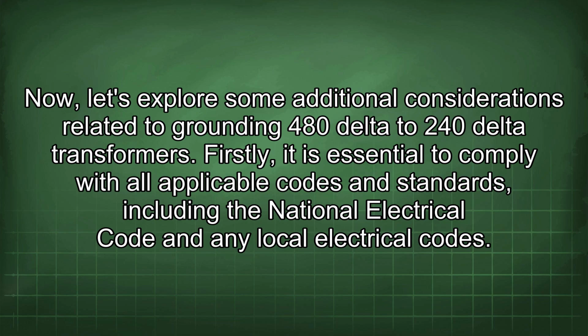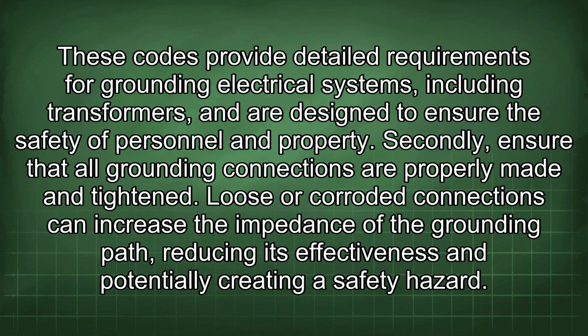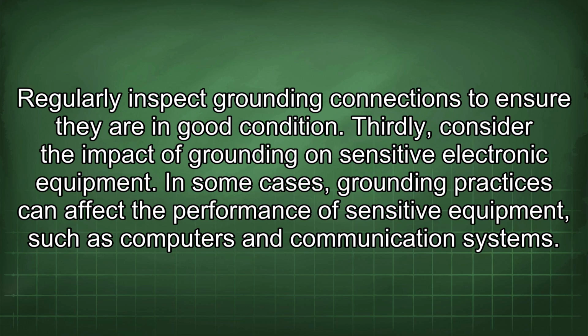Now, let's explore some additional considerations related to grounding 480 delta to 240 delta transformers. Firstly, it is essential to comply with all applicable codes and standards, including the National Electrical Code and any local electrical codes. These codes provide detailed requirements for grounding electrical systems, including transformers, and are designed to ensure the safety of personnel and property. Secondly, ensure that all grounding connections are properly made and tightened. Loose or corroded connections can increase the impedance of the grounding path, reducing its effectiveness and potentially creating a safety hazard. Regularly inspect grounding connections to ensure they are in good condition.